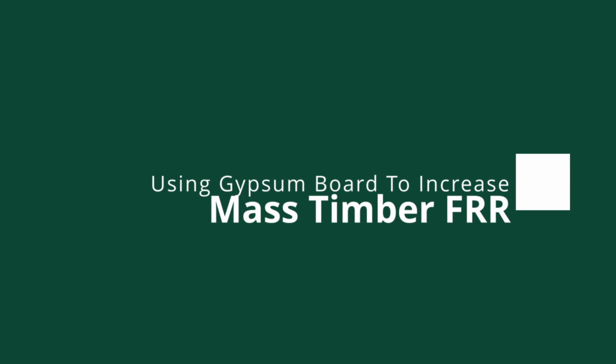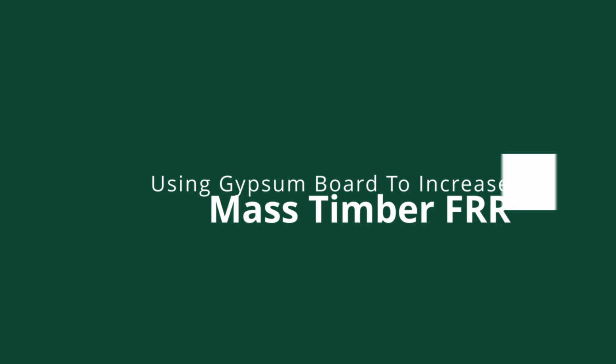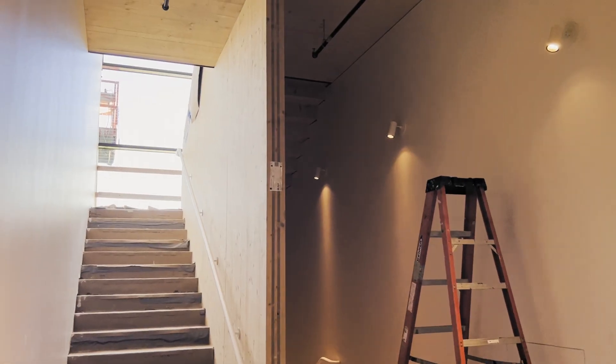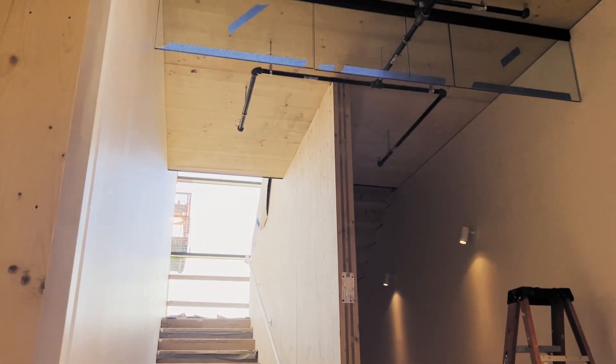When designing mass timber buildings, in most cases you want to expose the mass timber within the building to the maximum extent possible. However, there are certain applications, whether due to design restrictions, project-specific circumstances, or other requirements, which would either require or desire the direct application of gypsum wallboard to the mass timber members. If we are doing this, it might make a lot of sense, and in some cases be necessary, to use that direct applied gypsum wallboard to enhance the fire resistance rating of the timber members.